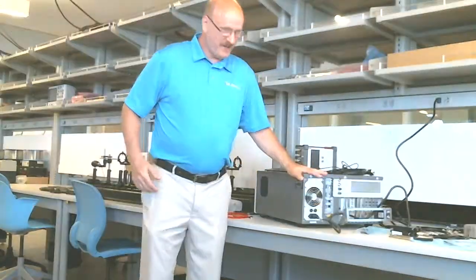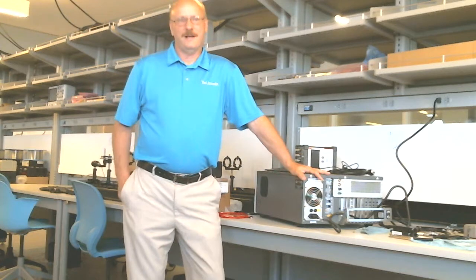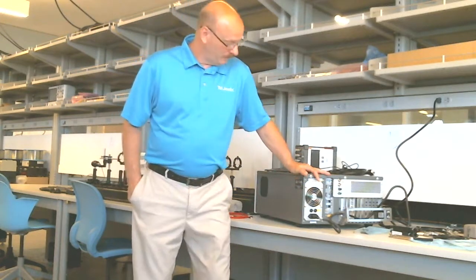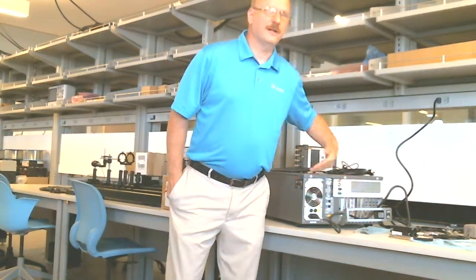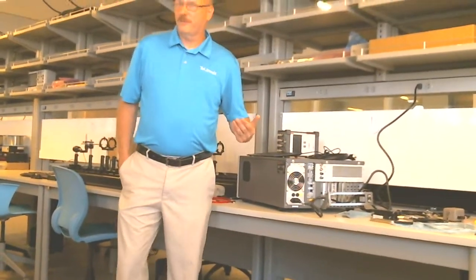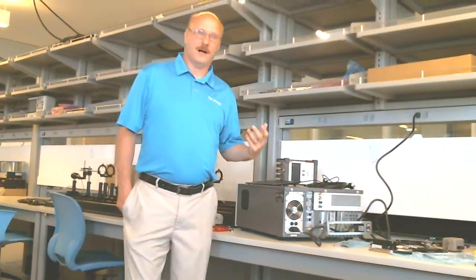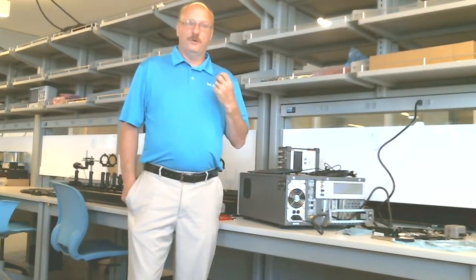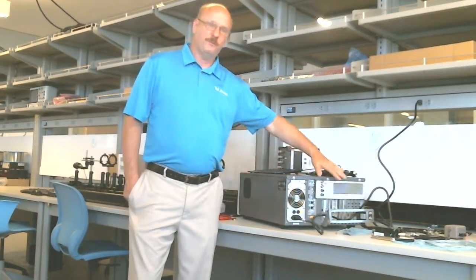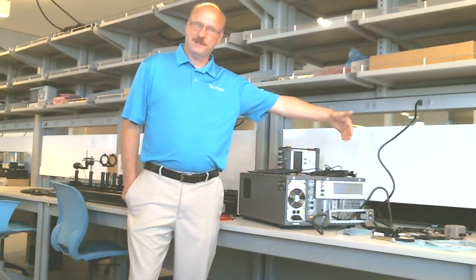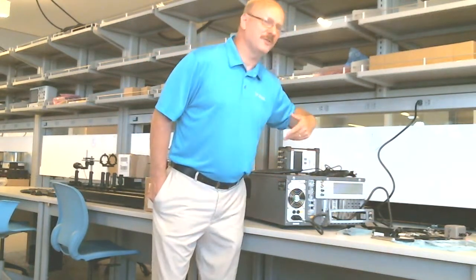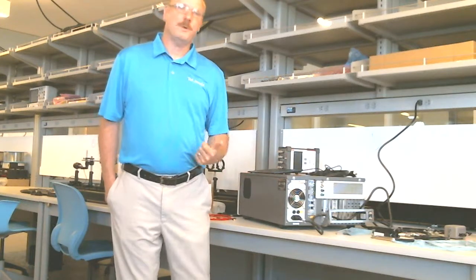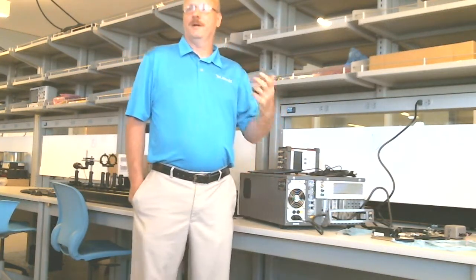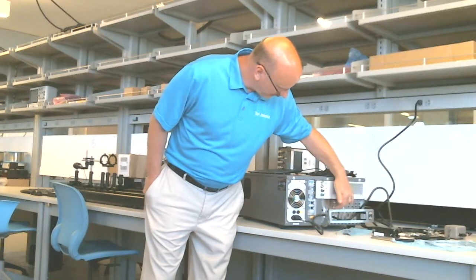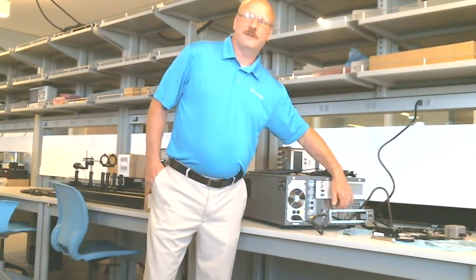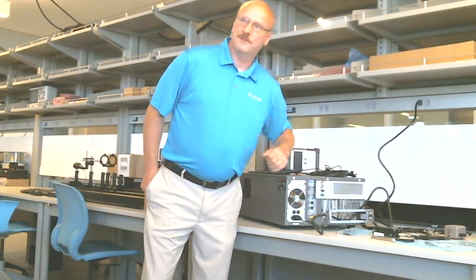We've got a chassis. The chassis has a backplane with 9 slots in it that you can outfit with different cards. The typical cards would be SMUs. We have 2 different SMUs. You bought 4 of the same, so you've got 4 SMUs. You've got 9 slots. You could put SMUs, you could put pulse cards in there, you could put a scope card, a function generator, or an LCR meter. You've got the LCR meter, that's what you see with the gold connectors there. So you've got the LCR meter, and you've got 4 SMUs.